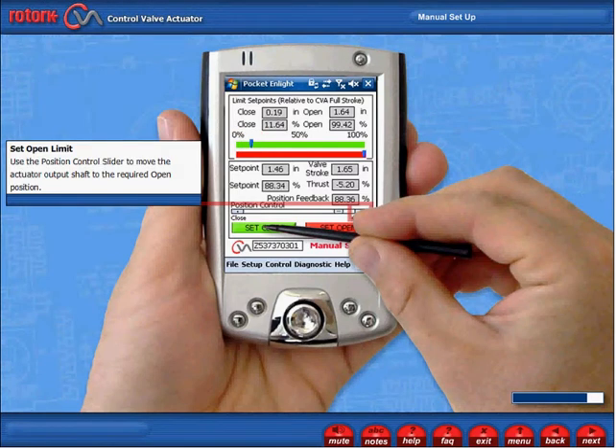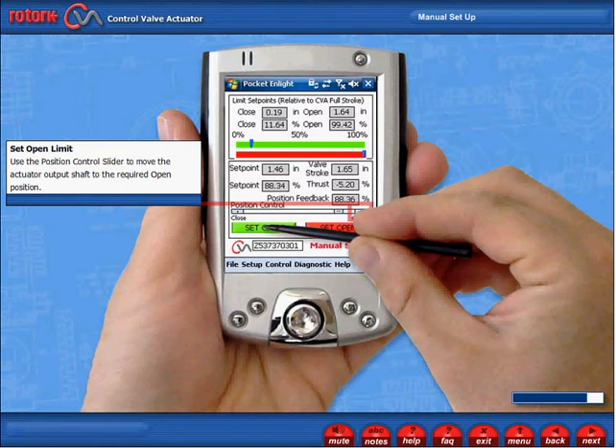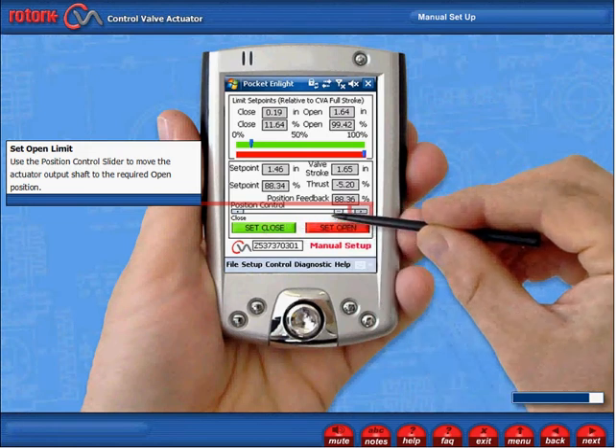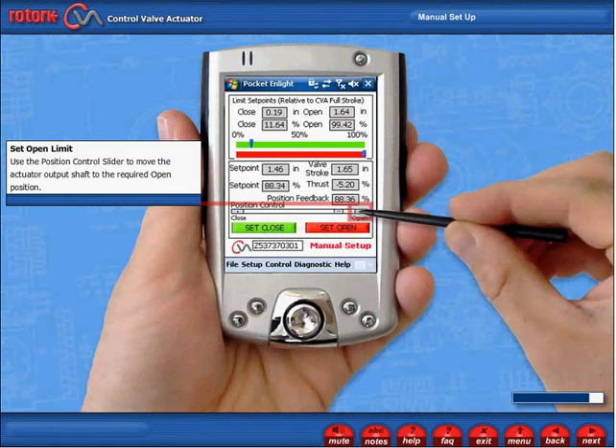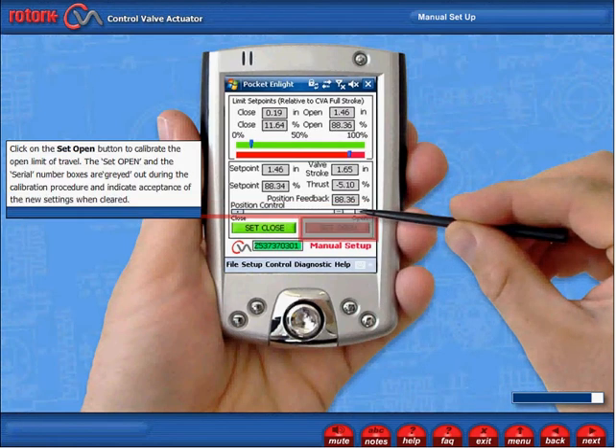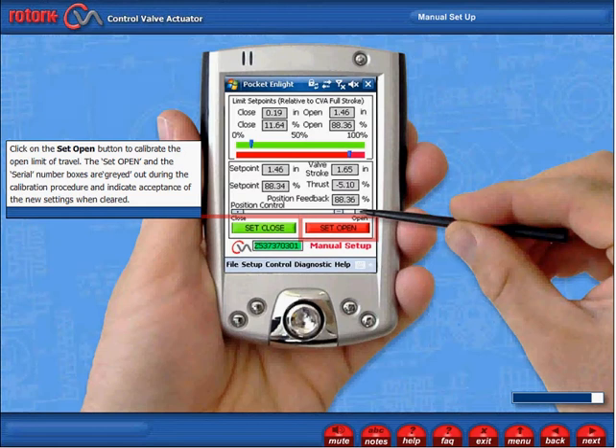Set Open Limit. Use the position control slider to move the actuator output shaft to the required open position. Click on the Set Open button to calibrate the open limit of travel.